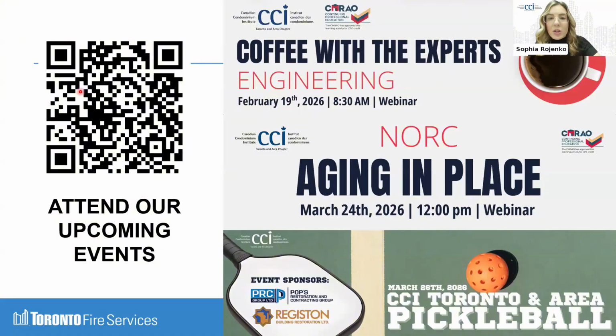Okay, next question is, a corporation allows owners to change their unit door lock by themselves and have different locks. There is no specific master key for all units. Is there any fire code issue, and if so, how do we handle it? There's nothing in the fire code that requires there to be a master key to dwelling units. So that's up to you how you want to run that. If there's a fire, firefighters will break the door in safely, considering the safety of occupants. But no, we do not need a master key of any kind into tenant spaces. We want service room keys, and that's it. Obviously, it's ideal to have access to dwelling units in an emergency, but nothing for us to enforce there. Nothing.